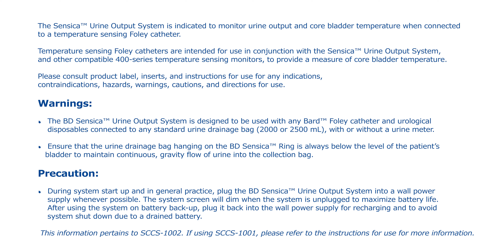Precaution. During system startup and in general practice, plug the BD Sensica urine output system into a wall power supply whenever possible. The system screen will dim when the system is unplugged to maximize battery life. After using the system on battery backup, plug it back into the wall power supply for recharging and to avoid system shutdown due to a drained battery. This information pertains to SCCS 1002. If using SCCS 1001, please refer to the instructions for use for more information.